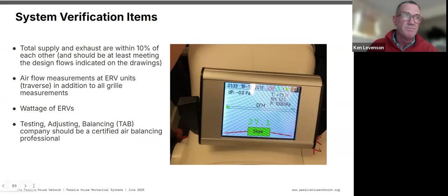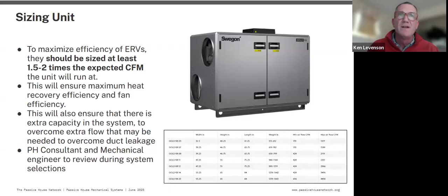One aspect is we want to essentially oversize the ventilation system. We want it to run at half capacity. This allows it to run most efficiently, and allows for any new needs for boost. It also allows for potential leakages to be overcome. You don't want to run out of capacity, and you don't want it running at a relatively high rate all the time for efficiency, both in heat recovery and energy use. You go bigger, let it run at a nice, comfortable trot.